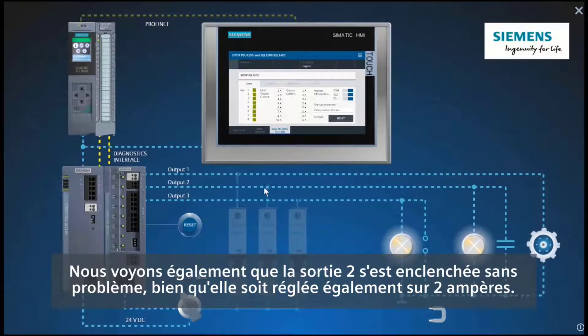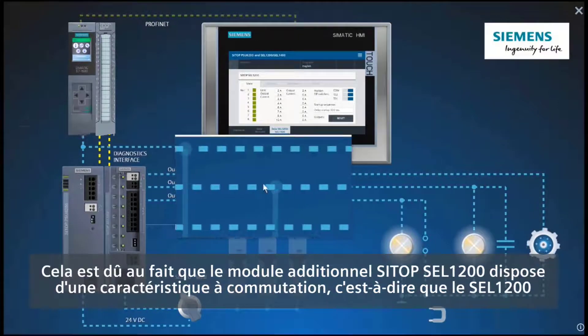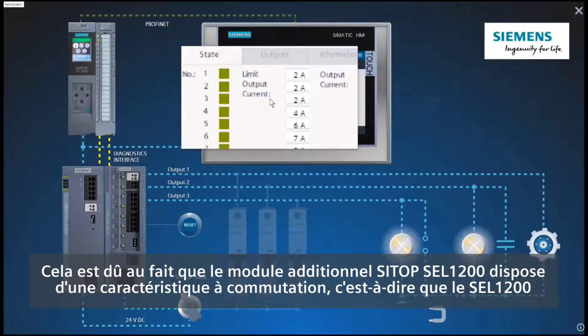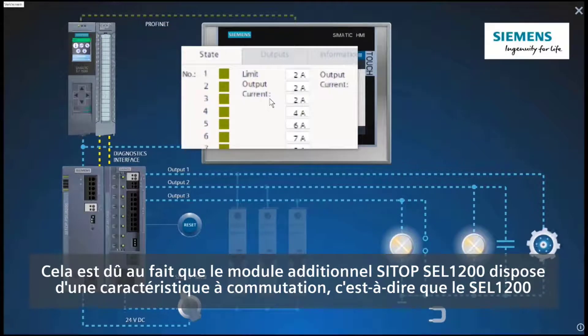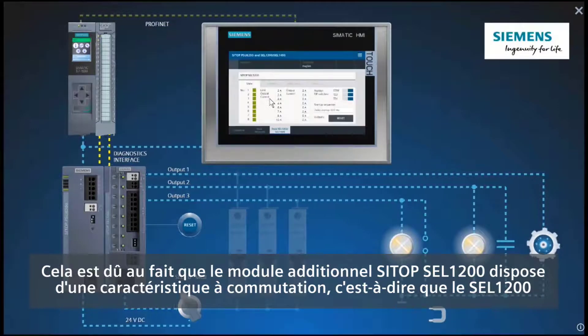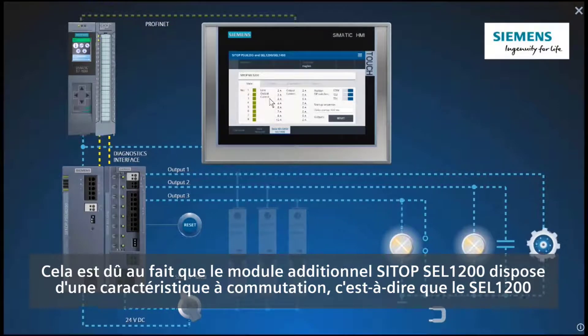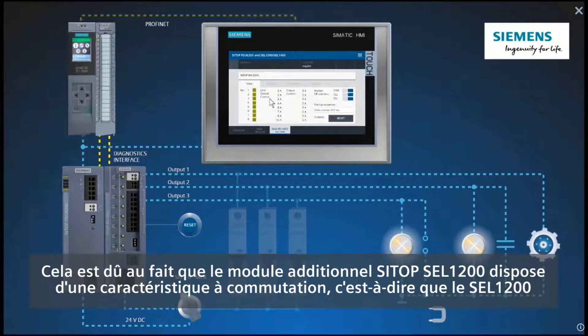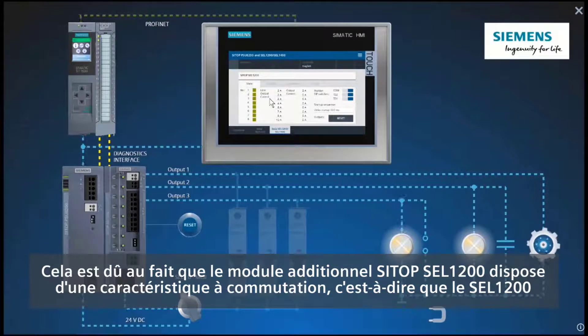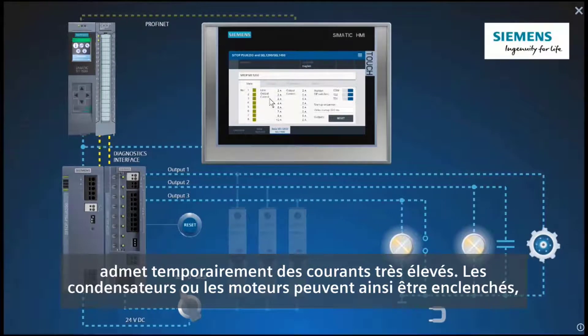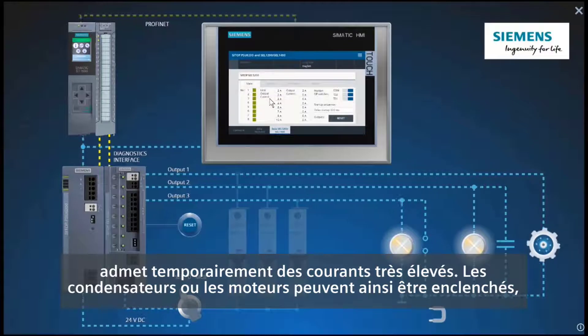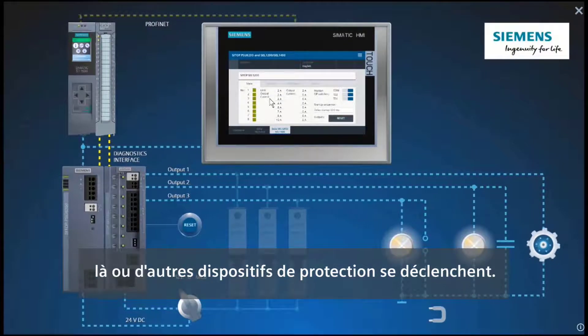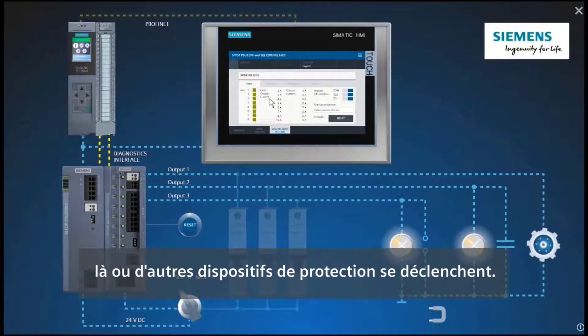Although it is also set to 2A. This is because the SITOP SEL1200 add-on module has a switching characteristic which means that the SEL1200 allows very high currents for a short time. This enables capacitors or motors to be switched on where other protective devices would trip.